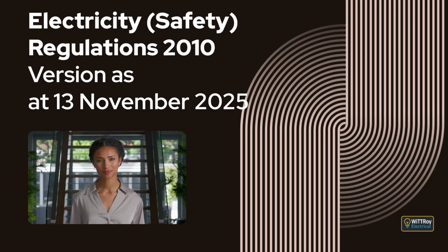The regulation then explains that an owner who keeps an installation in service commits an offence if a required periodic assessment is not carried out. It also explains that a person who carries out an assessment commits an offence if they are not authorized or do not have the required competencies, or if they fail to complete the record of assessment as required. It further explains that a person commits an offence if they use an installation that is required to be periodically assessed knowing that the assessment was carried out by someone to whom those offence provisions apply. The regulation finishes by explaining that, to avoid doubt, the assessment requirements and the assessment intervals set out here apply despite anything to the contrary in the reference standards.